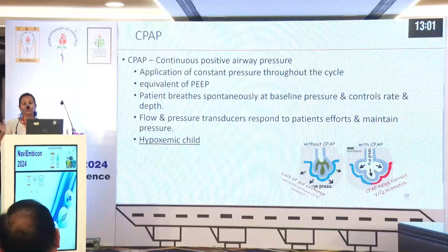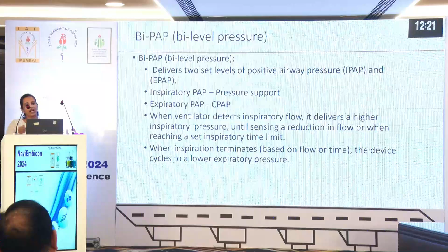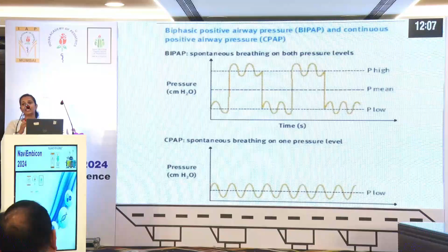Then there is BiPAP. In BiPAP, you deliver two sets of positive airway pressure, the IPAP and the EPAP. The IPAP is the inspiratory positive airway pressure or the pressure support, and the EPAP is the expiratory pressure, which keeps the airway open in the expiration. So the ventilator detects inspiratory flow. It delivers a high inspiratory pressure until it senses a reduction in the flow or when it reaches a set inspiratory time limit. So the inspiration terminates based on flow or time, and the device cycles to the lower expiratory pressure. This is how the breathing occurs on both the modes. In BiPAP, there is spontaneous breathing on both pressure levels, while in CPAP, there is spontaneous breathing on one pressure level.